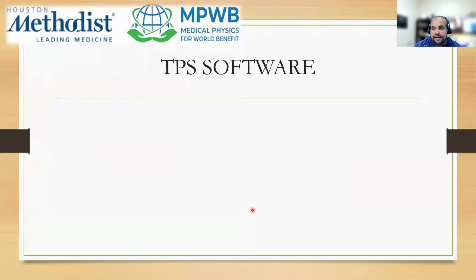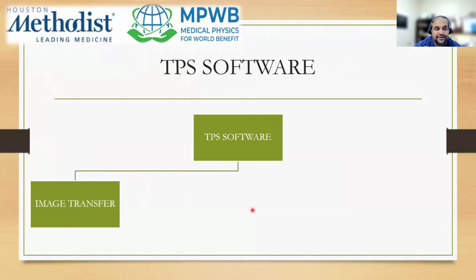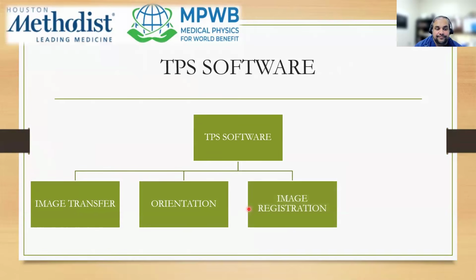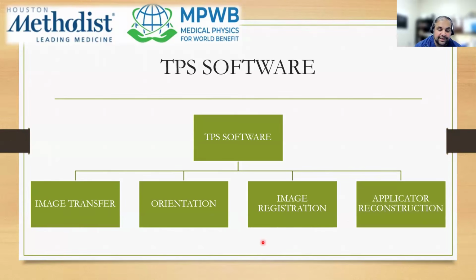So for your treatment planning system software, you have your image transfer. You need to CT your applicator. You then check the orientation. Does it match what you expect? Are there any image registrations that you can do and test? Typically for brachytherapy, you have MRI and PET images, and then of course your applicator reconstruction. And in the end, there's always the end-to-end test that needs to be done.